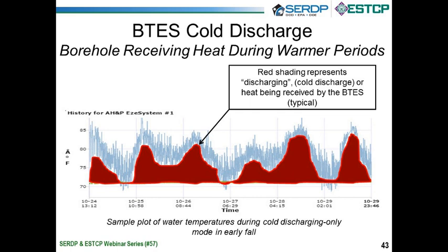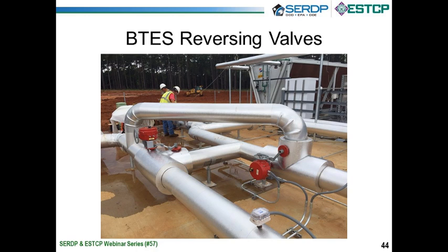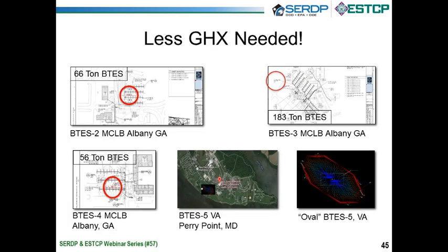This is back in the fall. We're dumping heat all the time. So water's going in and out at 75, 85 degrees, coming back in the low 70s. That's dumping heat into the BTES. These are the reversing valves, really just a couple of three-way valves like you'd see on any chilled hot water system. They allow us to route the water in and out of the core depending on whether we're charging or discharging. You can see the adiabatic dry coolers in the background.